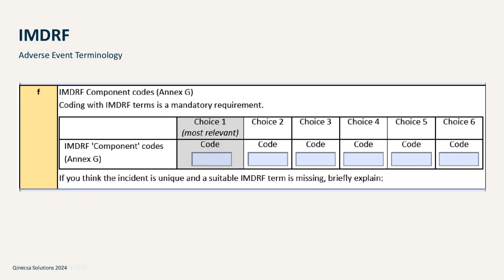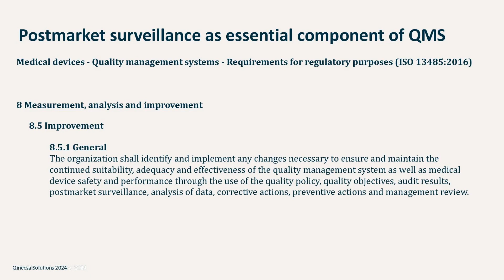Quality management system, ISO 13485, that's the most essential ISO standard in medical devices, and post-market surveillance is an essential component of the quality management system. The biggest part is complaint handling procedure. The definition of a complaint needs to be very broad because it needs to cover all jurisdictions where the manufacturer is marketing their devices.